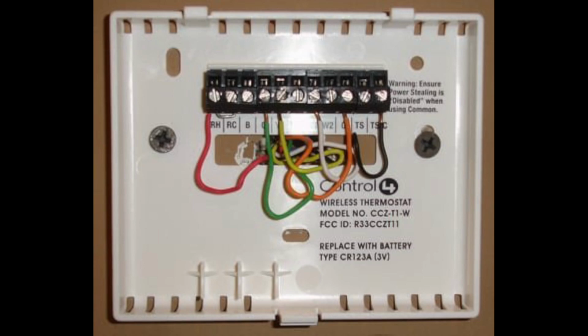And remember, it has a warning. It says ensure power is disabled when you're doing any kind of connections. Here's something I want you guys to understand. If you're going to change your thermostat, you need to go to your furnace. You need to find the breaker, or if you have an indoor power supply to it, which most of them do by city code, you need to turn the power off to your indoor unit before you mess around with this. Because if you arc any of those wires, you will pop the 5 amp fuse on it or 3 amp fuse, and or potentially burn out your transformer. You have to turn your power off if you're going to do any thermostat maintenance.